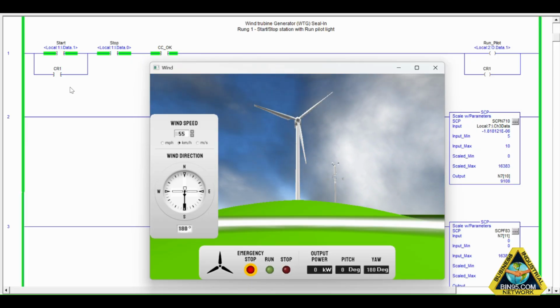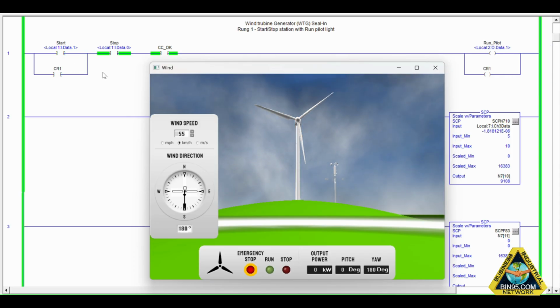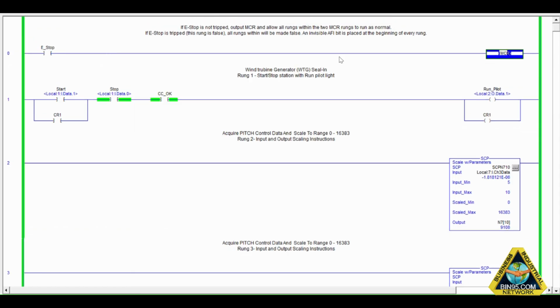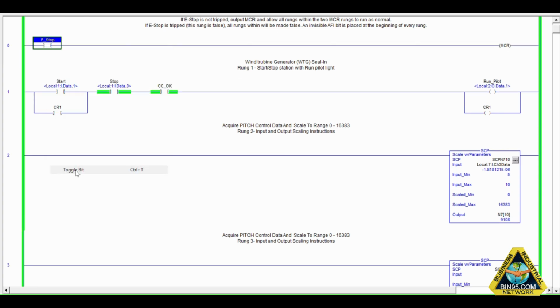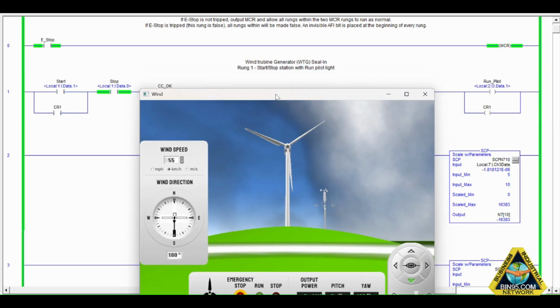The rung is true, but the output is not true? That is just not logical. To check whether an MCR is the culprit, scroll upward in the subroutine and look for an MCR output instruction above the illogical rung. If that conditional MCR rung is false, toggle its controlling bit in the simulator. Once MCR becomes true, all rungs inside the zone behave normally. As shown here, using the RSLogix 5000 PLC training simulator.